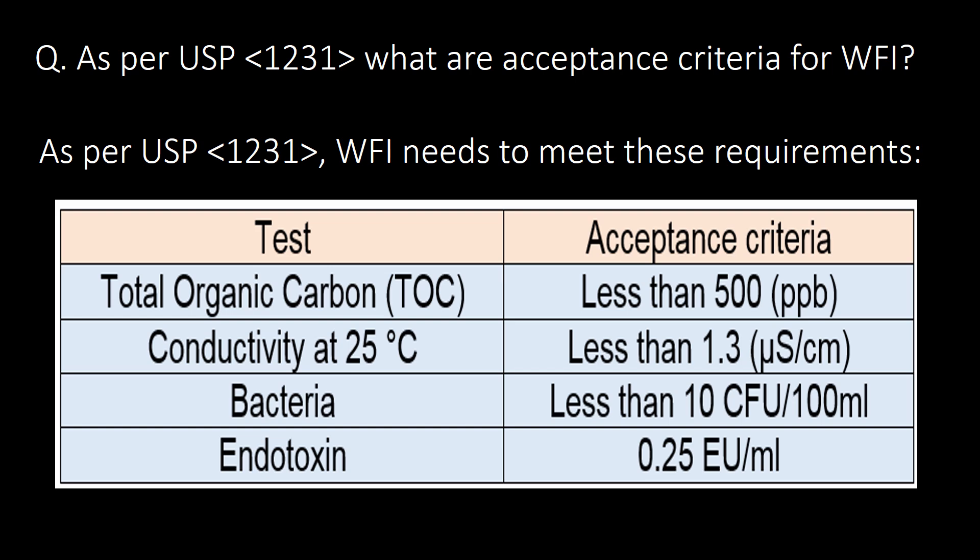First test is TOC, that is total organic carbon testing; acceptance criteria is less than 500 ppb. Second test is conductivity at 25 degrees Celsius; acceptance criteria is less than 1.3 micro siemens per centimeter. Third test is bacteria; acceptance criteria is less than 10 CFU per 100 ml, where CFU stands for colony forming units. Fourth important test is for endotoxin; acceptance criteria is 0.25 EU per ml, where EU stands for endotoxin units.